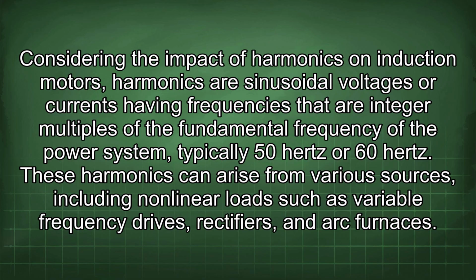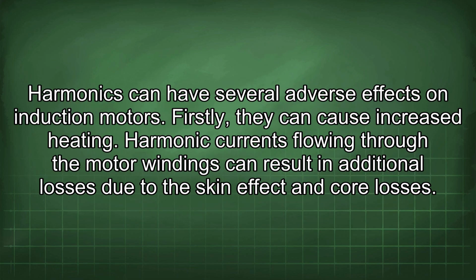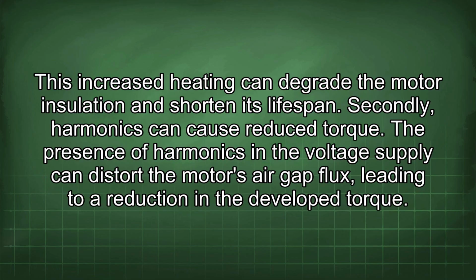Considering the impact of harmonics on induction motors, harmonics are sinusoidal voltages or currents having frequencies that are integer multiples of the fundamental frequency of the power system, typically 50 Hz or 60 Hz. These harmonics can arise from various sources, including nonlinear loads such as variable frequency drives, rectifiers, and arc furnaces. Harmonics can have several adverse effects on induction motors. Firstly, they can cause increased heating. Harmonic currents flowing through the motor windings can result in additional losses due to the skin effect and core losses. This increased heating can degrade the motor insulation and shorten its lifespan.